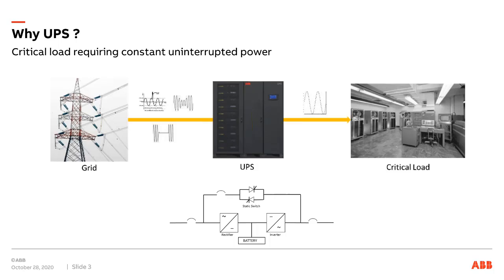to the critical load. What makes it uninterrupted is that the battery that's connected, connecting DC power to that same DC bus, the inverter doesn't care whether it's getting DC power from the rectifier or from the battery. As long as there's power on one of them, it's good to go. So that's the uninterrupted part. If power from the utility fails, the inverter will continue on the battery. And if power stays out from the utility, hopefully there's a generator that can kick in and start feeding the rectifier. Other than that, it'll be over when the battery runs out.